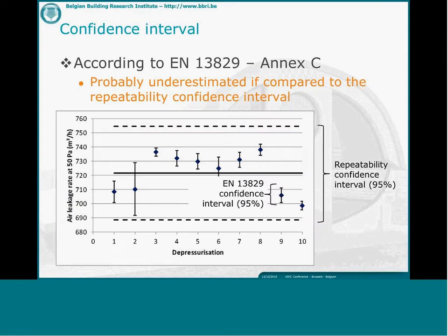We can also compare the confidence interval calculated according to Annex C of the European standard. But you see on the chart, probably this is underestimated if we compare it to the repeatability confidence interval we obtained with the measurements. Maybe it's a good idea to revise it or to calculate it otherwise, but this is now under discussion in the revision of ISO 9972.